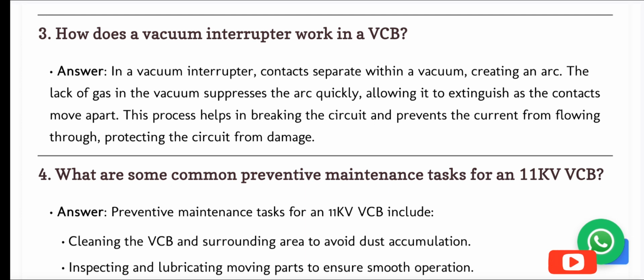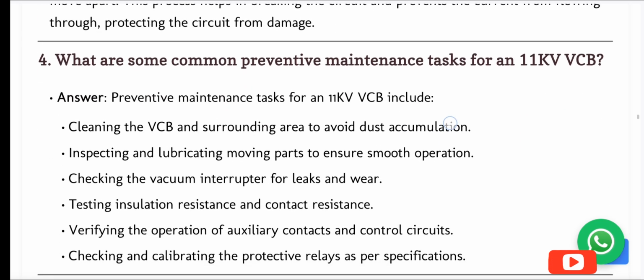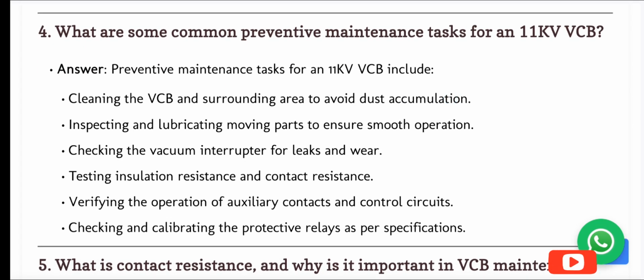Answer. In a vacuum interrupter, contacts separate within a vacuum, creating an arc. The lack of gas in the vacuum suppresses the arc quickly, allowing it to extinguish as the contacts move apart. This process helps in breaking the circuit and prevents the current from flowing through, protecting the circuit from damage. 4. What are some common preventive maintenance tasks for an 11 kV VCB?